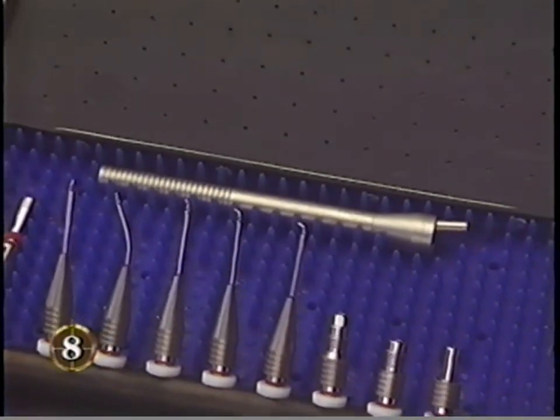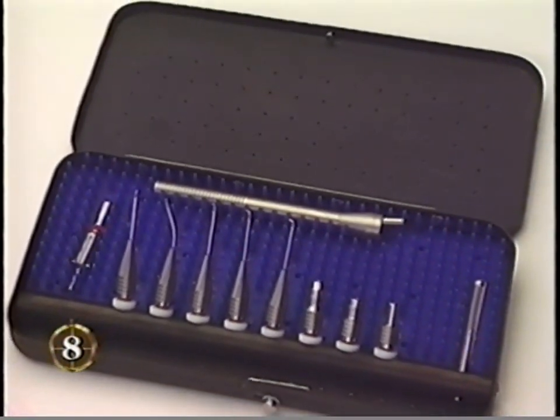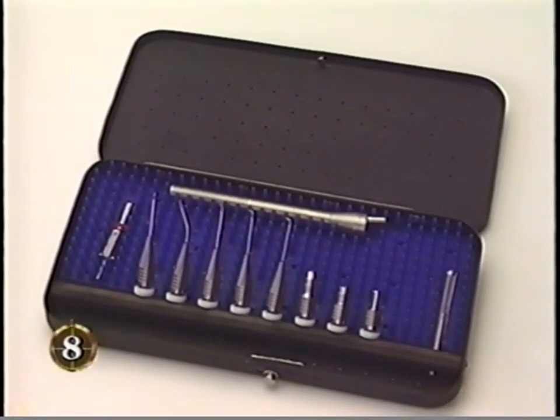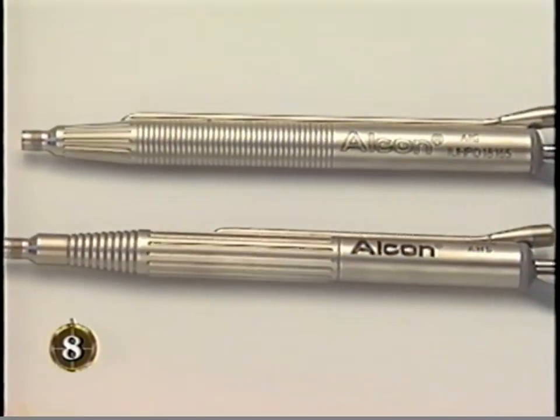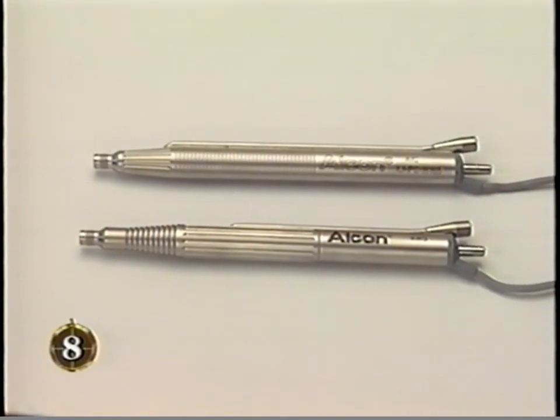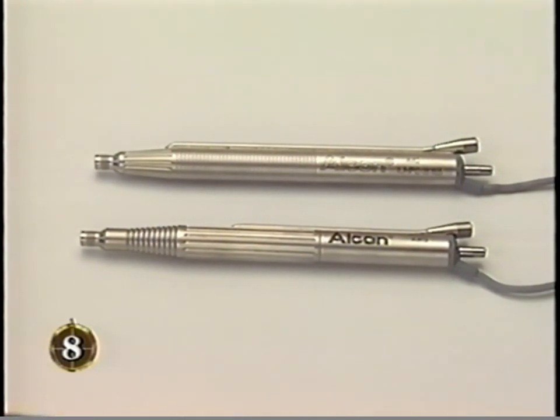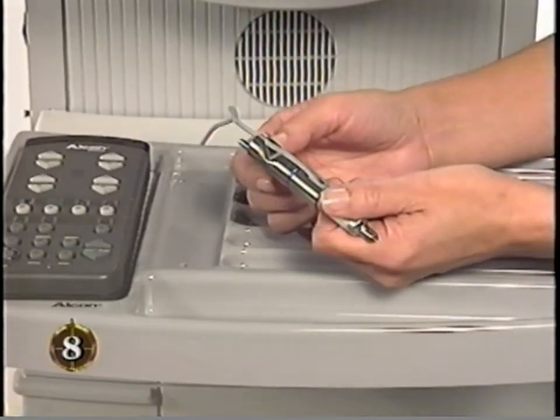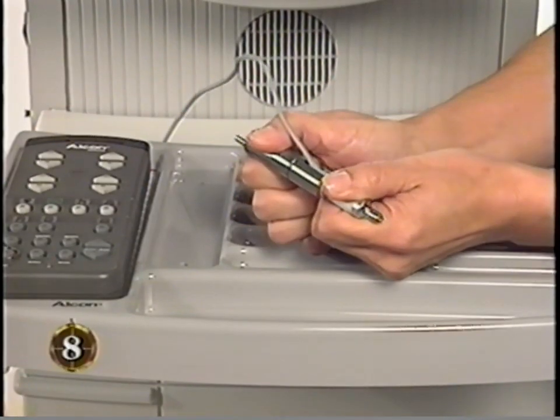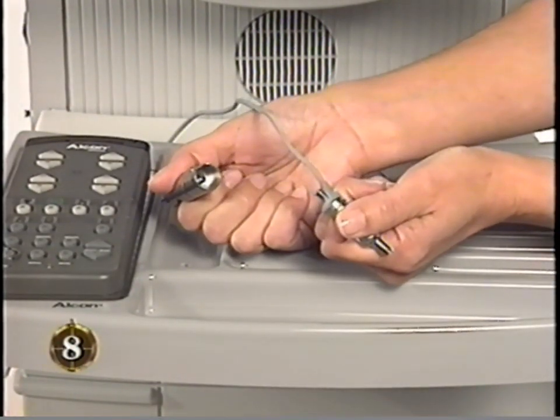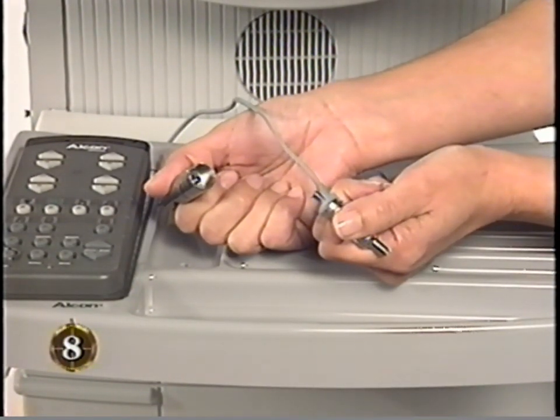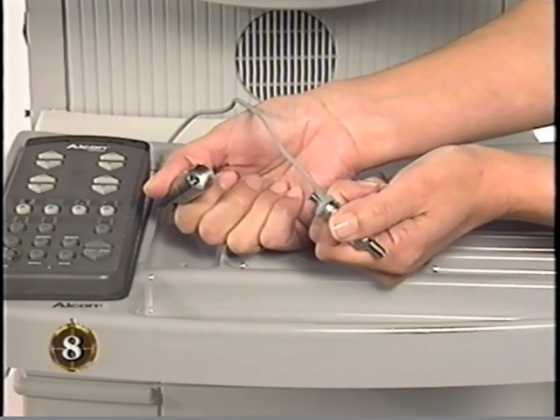Reusable irrigation and irrigation aspiration handpieces and tips may be gas, flash, or steam autoclaved. Ultrasound handpieces and reusable coagulation handpieces should only be flash or steam autoclaved. The sterilization reservoir should be filled with distilled or deionized water. The hydrosonics handpiece and the injector portion should be separated and steam autoclaved unwrapped at 132 degrees Celsius or 270 degrees Fahrenheit.